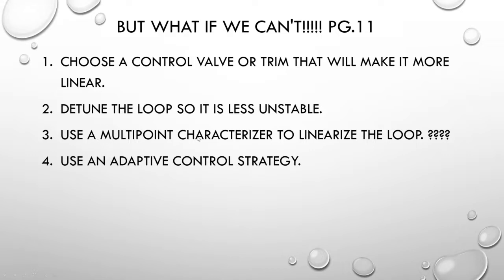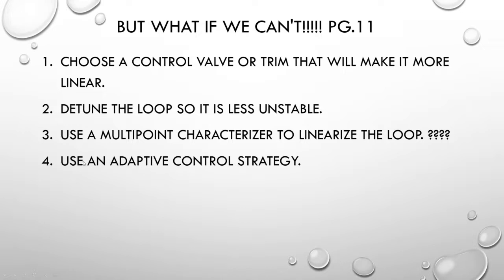The third option is to use something called a multipoint characterizer to linearize the loop. A characterizer is a method of plotting the response as it sits, then programming the controller to output a different value relative to our location in the range in order to linearize or straighten the line. Finally, the most complicated method is using an adaptive control strategy, which applies different tuning values at different points in the operating range based on calculations.